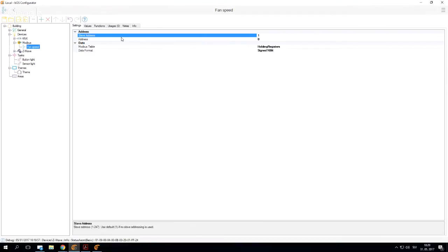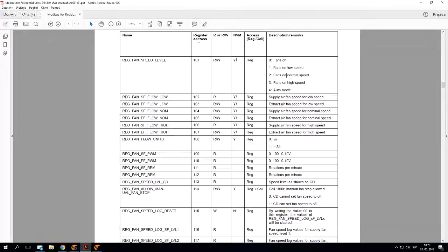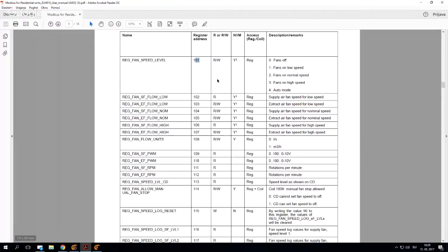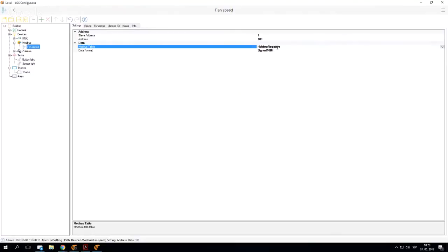The Modbus will send the correct values to each device. I need to enter my address of this fan speed. As you can see here under registers, their address is 101. So I must link this correctly and say this is 101. Since this is a read and write value, we're going to use our holding registers, which is already selected.